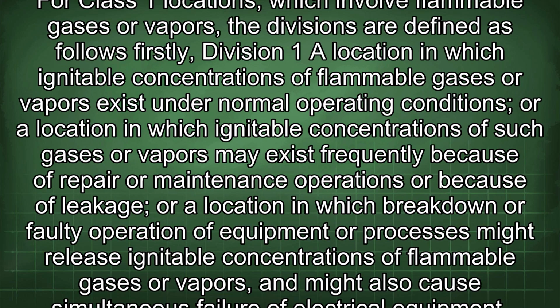For Class 1 locations, which involve flammable gases or vapors, the divisions are defined as follows. Firstly, Division 1: a location in which ignitable concentrations of flammable gases or vapors exist under normal operating conditions, or a location in which ignitable concentrations of such gases or vapors may exist frequently because of repair or maintenance operations or because of leakage, or a location in which breakdown or faulty operation of equipment or processes might release ignitable concentrations of flammable gases or vapors, and might also cause simultaneous failure of electrical equipment.